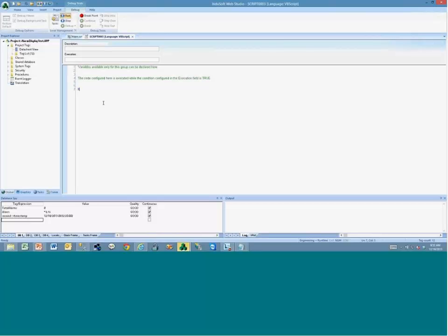So you can say here, again, using the timestamp. If I use the syntax X timestamp, it returns the timestamp with milliseconds. If you use the function getElement with dot as the delimiter, the first one, this whole syntax returns the timestamp of the tag X. In other words, the last date and time when the tag X changed value, but without the milliseconds. So you can say, if the date difference between the last time when the tag X changed and now is greater than, let's say, 3 seconds, right? If we are making the comparison with seconds.